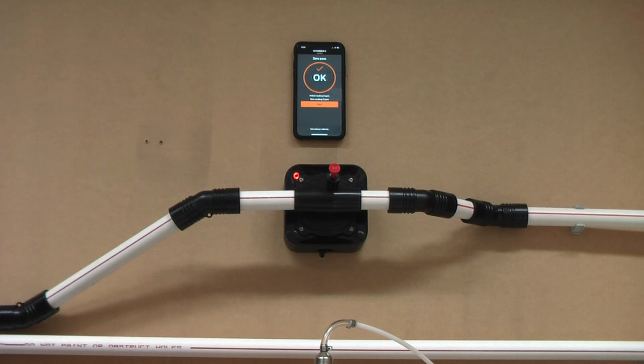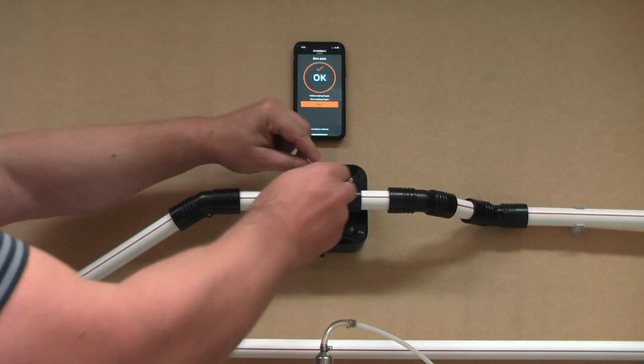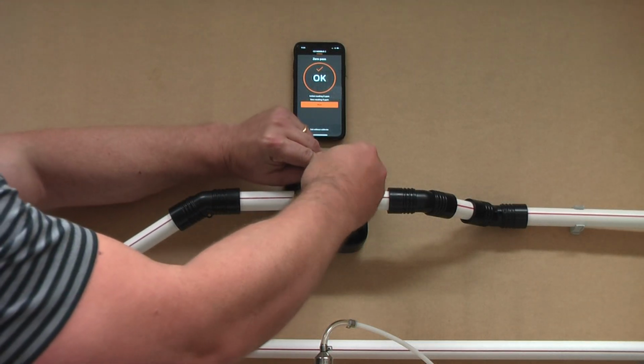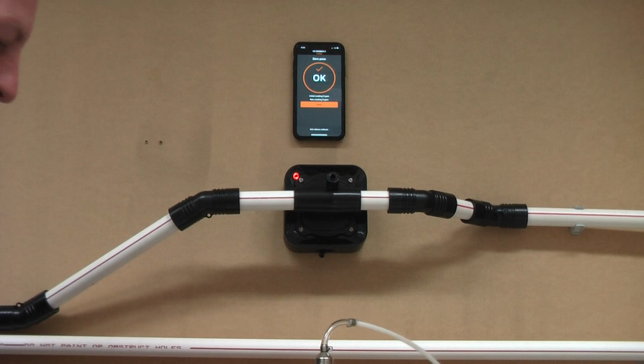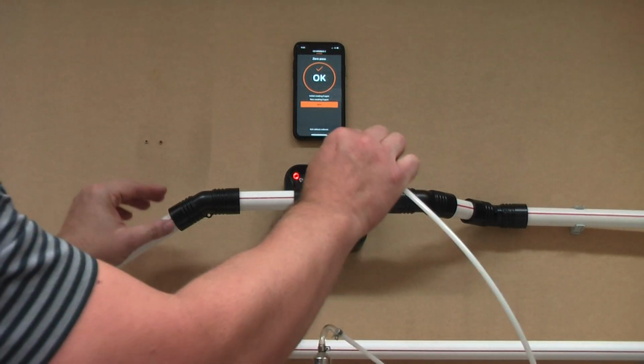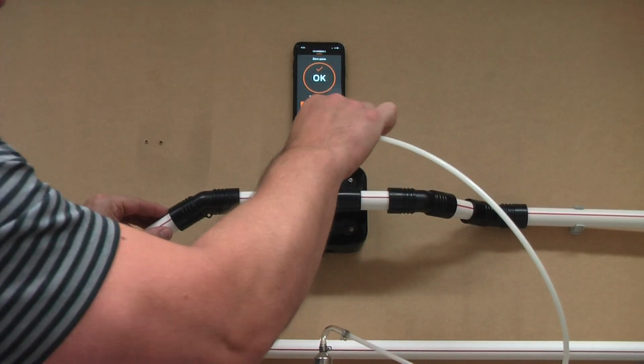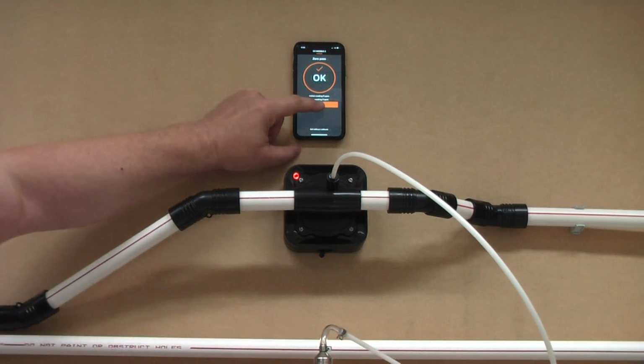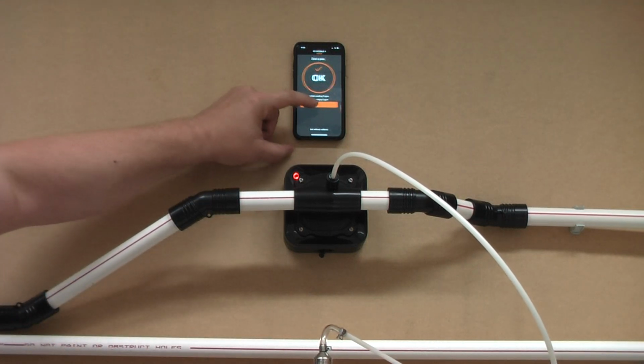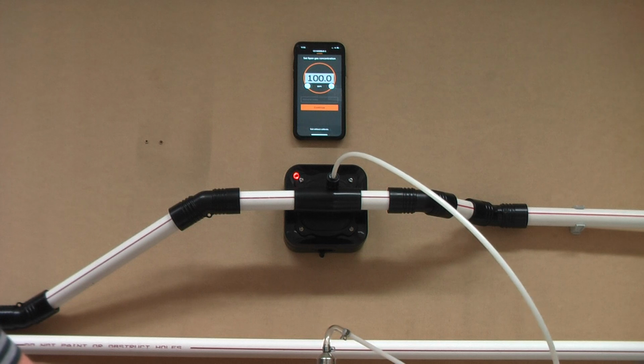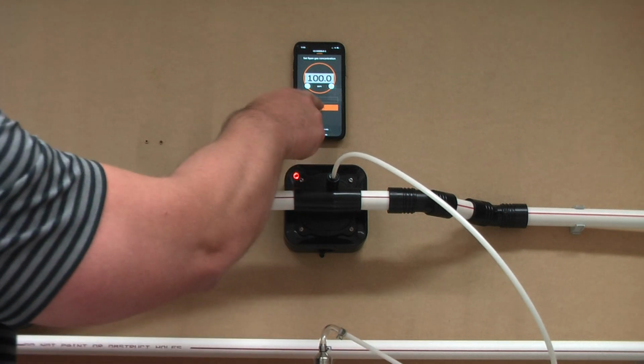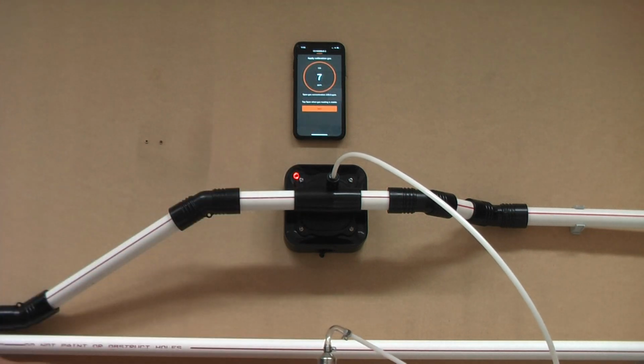I need to apply some gas to the detector and let it go into the next phase, which is called the span phase. So I remove this port and I apply the tube into the port, calibration port, and then I can push next. And as I do that, I open the valve and apply gas. Hit the continue button, noting my 100 parts per million.